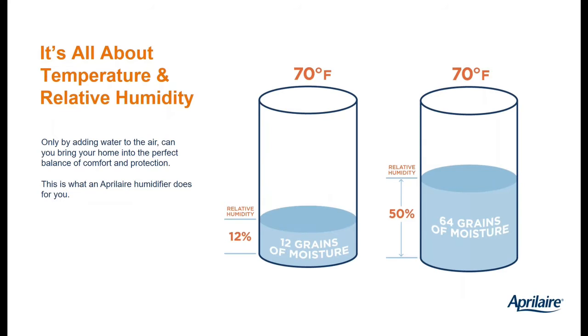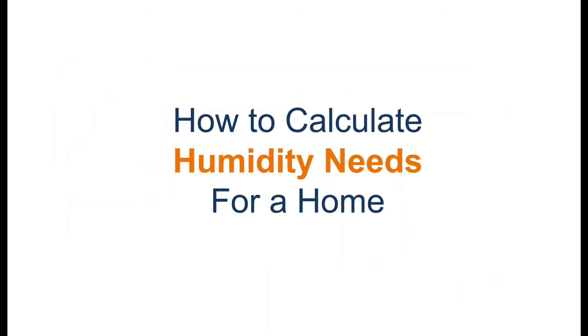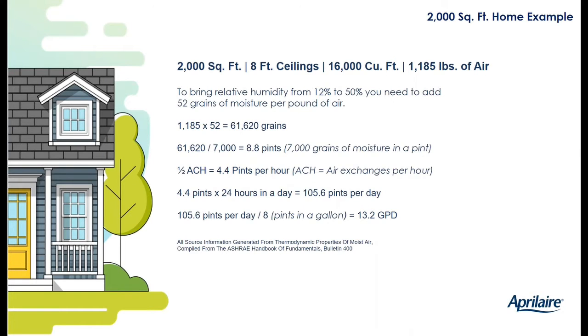So you can see in our example here, we add 52 grains of moisture per pound of dry air. That gets our relative humidity back up to 50%. And that's what an AprilAire humidifier does. Okay, I'm going to walk you through this calculation, and I'm going to show you we've already done all the hard work for you because we have a table. But this is the actual psychrometric calculation that you go through.